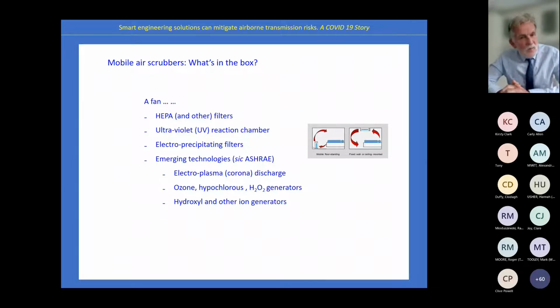A fan, one of Chris's HEPA filters and other filters maybe, an ultraviolet reaction chamber maybe, possibly an electroprecipitating filter. We'll talk about that in a moment. And maybe some emerging technologies. In ASHRAE, the American Society, they talk about these electroplasma, corona discharge, ozone, hypochlorous generators, and so on. The emerging technologies are interesting. They are not recommended by SAGE, and we are looking at those as possible solutions to infection transmission and mitigation of airborne pathogens in the future.